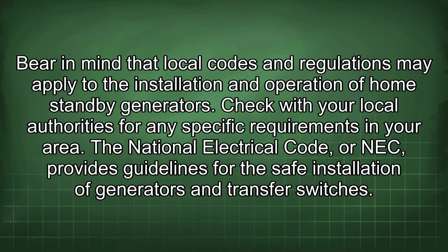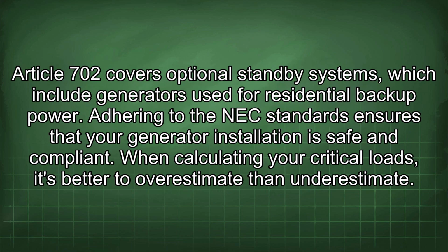The National Electrical Code, or NEC, provides guidelines for the safe installation of generators and transfer switches. Article 702 covers optional standby systems, which include generators used for residential backup power. Adhering to the NEC standards ensures that your generator installation is safe and compliant.